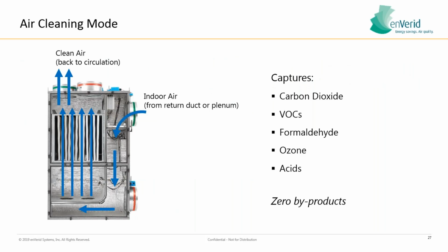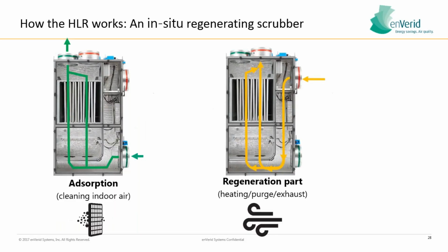So just going over the airflow patterns here, basically you've got those 2 muffin fans in there. You've got the 12 vertical V-bank cartridges as well, putting that clean air back into circulation. We're removing all these contaminants, including acids, with 0 byproducts, okay?